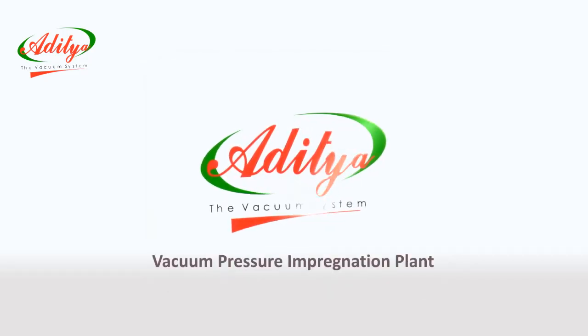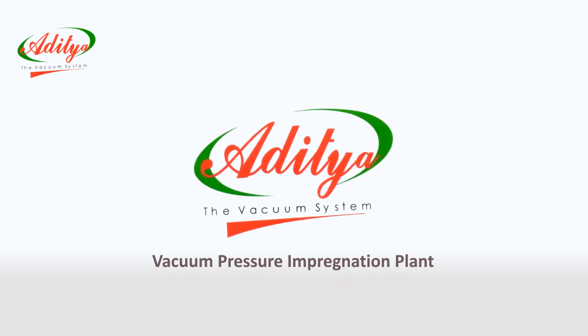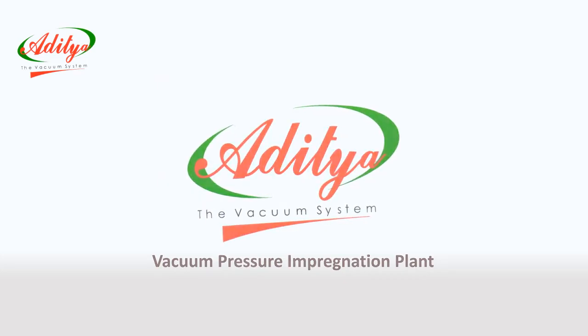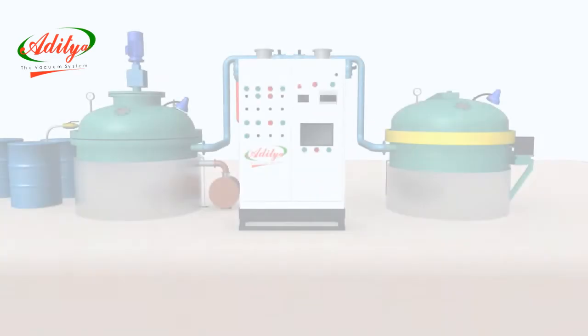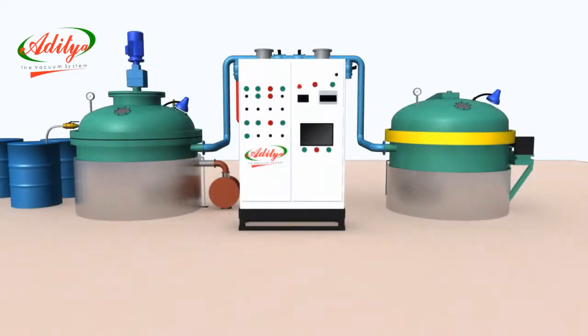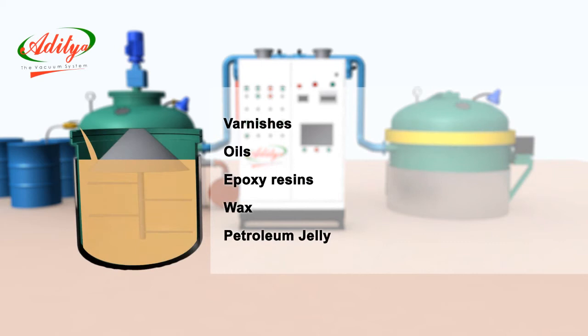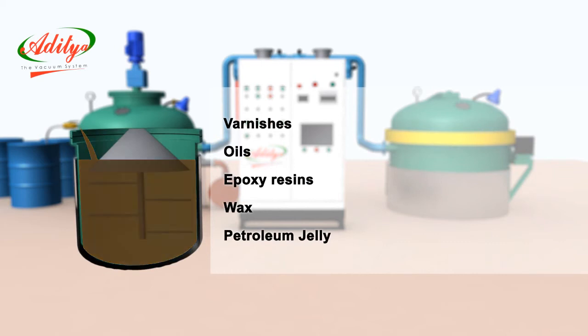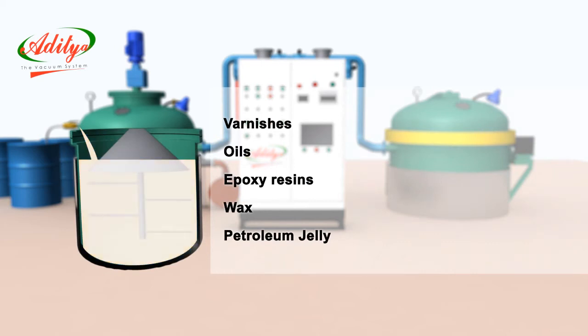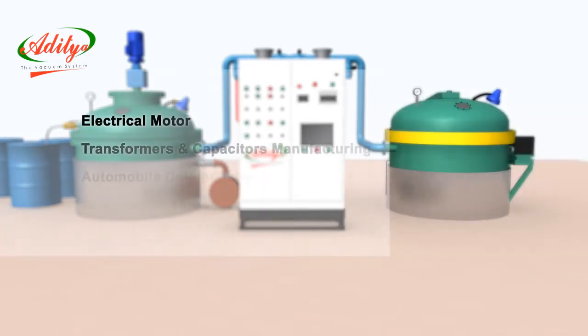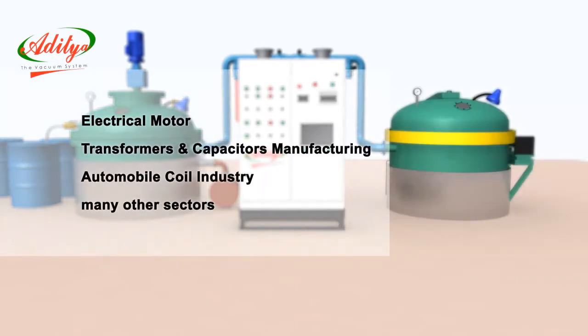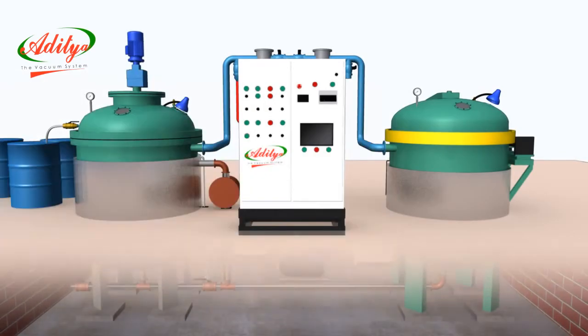Vacuum pressure impregnation process is required for impregnating coils of LT or HT machines. This process improves the insulation resistance, life and performance of components. The plants required for impregnation are specially designed for all types of varnishes, oils, epoxy resins, wax, petroleum jelly in electrical motor, transformers and capacitors manufacturing, automobile coil industry and many other sectors.